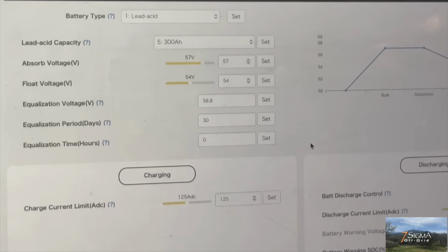If you deliberately charge the whole bank up to a higher set point and hold it there, every individual battery gets brought up and equalized at the very top, the very toppy top, all of them at the same true full state. That's what basically resets the calibration between your SOC and your voltage.